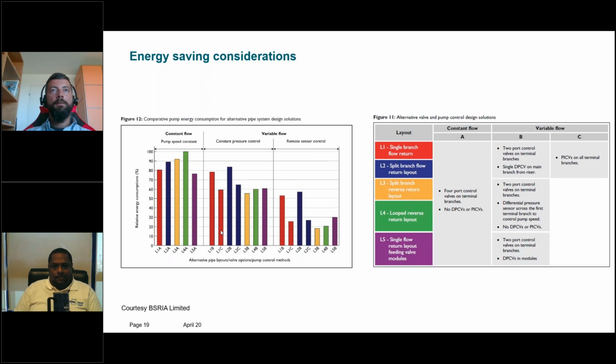Okay, I'll move on to the next question. If the building has two-way valves in the existing project, will the intelligent valve bring more saving if it is installed on the risers or on the branches? That's a yes, because then you can do this delta T control on the intelligent valve. I expect then that the two-way valves are just standard control valves. Yes, these are standard control valves which are in the existing building.